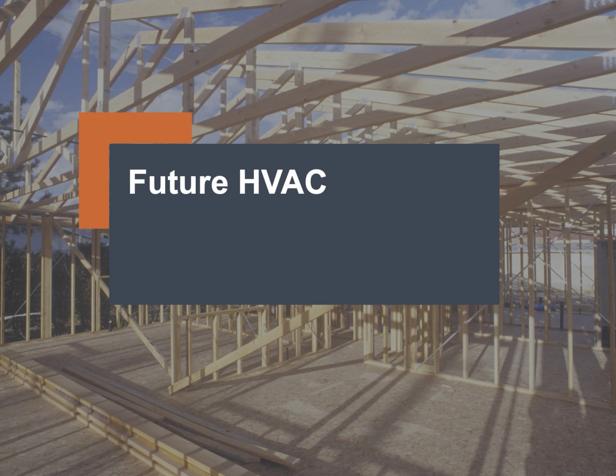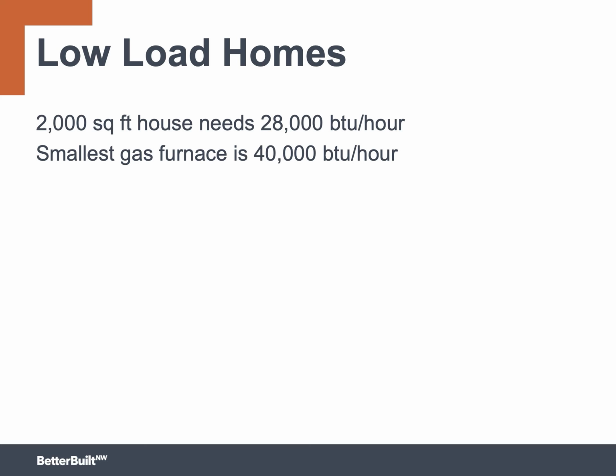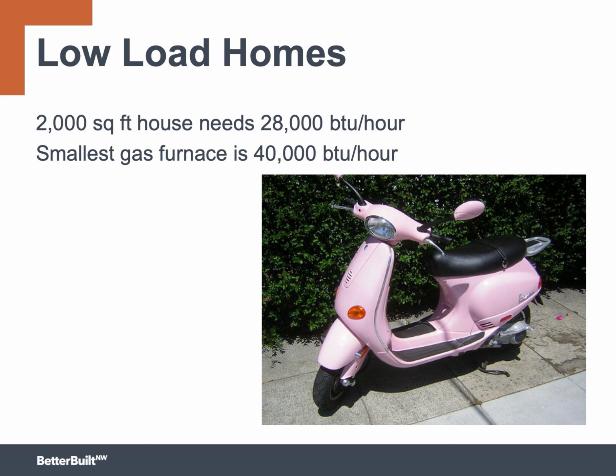Like everything else, the HVAC industry is developing advanced systems to meet the needs of the future. One huge change is the increasing energy efficiency of new homes. The design heat load of a 2,000 square foot house built to the Energy Star standard in the Pacific Northwest is about 28,000 BTUs per hour. Few manufacturers even make a furnace below 40,000 BTUs per hour, so you're automatically putting in an oversized furnace into that house. Not only that, but there's a strong push to reduce space conditioning loads even further. New initiatives such as Passive House and Net Zero Energy need far less, perhaps 10,000 BTUs per hour. And putting an oversized furnace in a house like that is like putting a V8 in a Vespa.